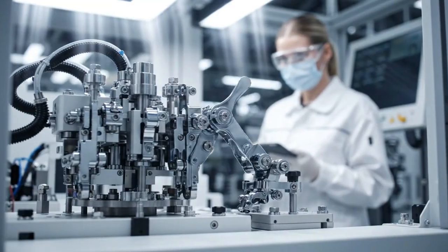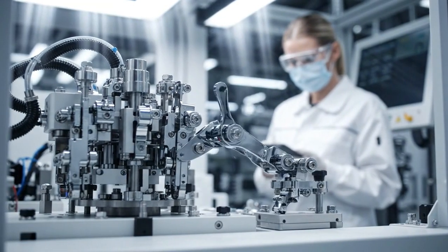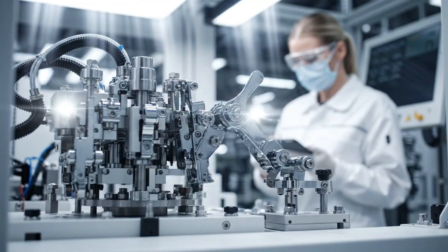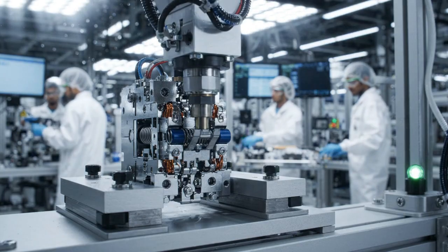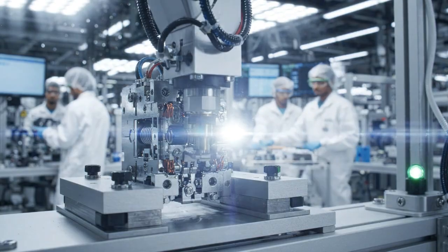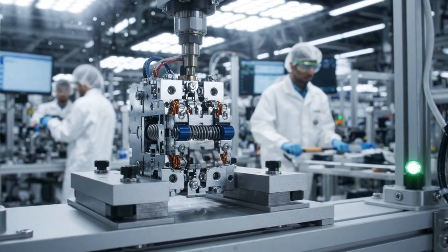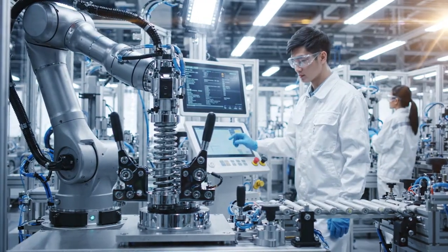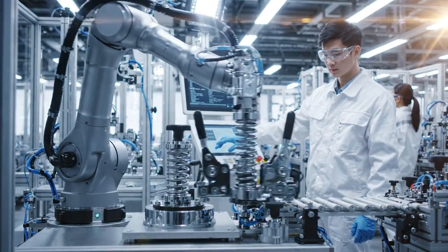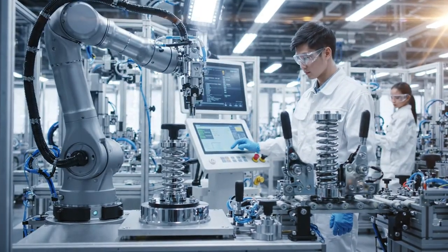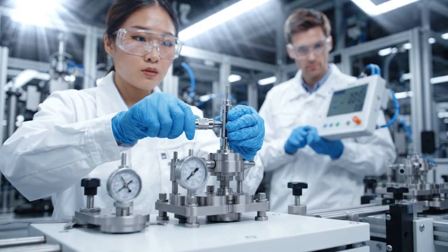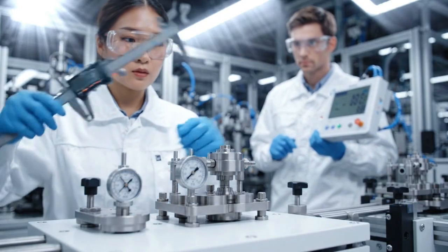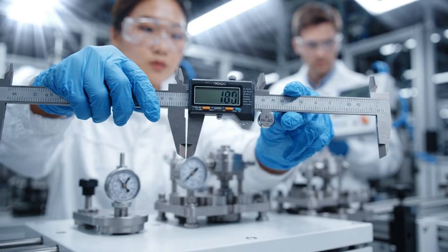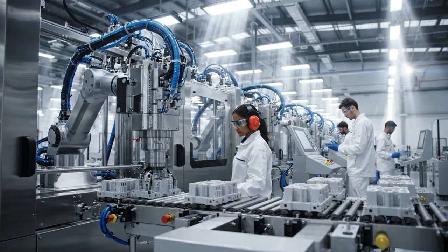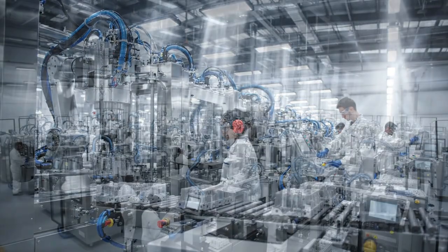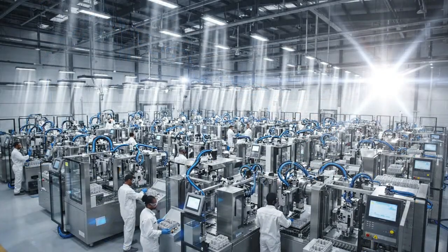The operating mechanism is a precision kinematic assembly. Lever ratios and latch geometry determine contact force, opening speed, and trip threshold. The trip-free mechanism prevents the user from holding the breaker closed during a fault condition. The mechanism trips and opens the contacts regardless of handle position. Housing molding uses glass fiber reinforced thermoset plastic that withstands the extreme temperatures and pressures generated when a breaker interrupts a severe short circuit.